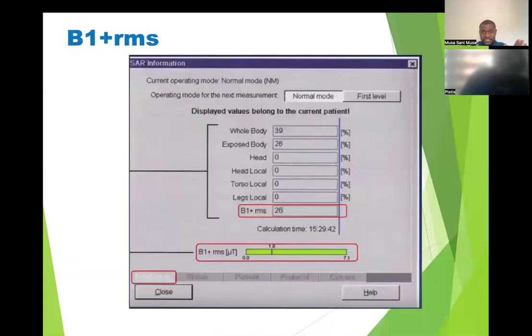So this is from Siemens. I don't know how this looks on a Philips or GE scanner, but this is on a Siemens. This is how you can monitor your patient. When you go to SAR information, it tells you your B1 plus root mean square, making sure you're scanning within the acceptable level. On a normal SAR mode, this is it. If you go to a first level mode, it changes. So this is how you keep track, to make sure you're scanning within the acceptable limit.